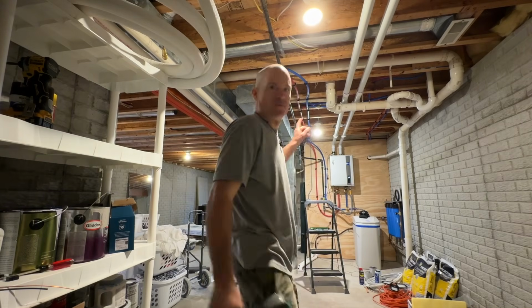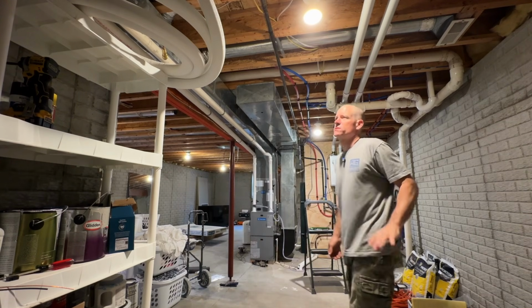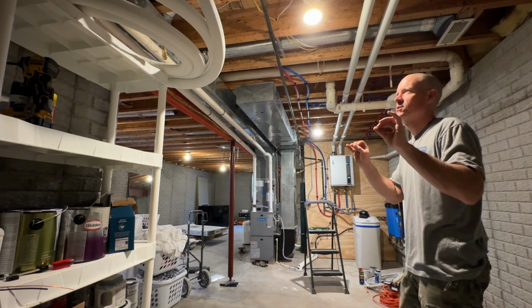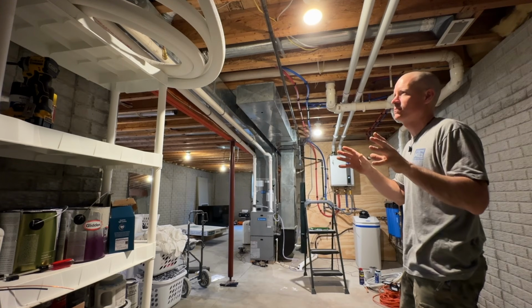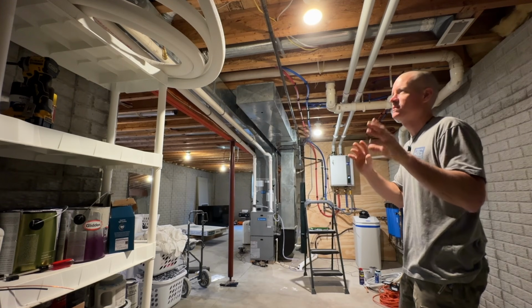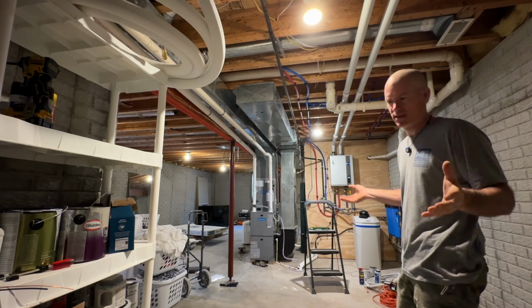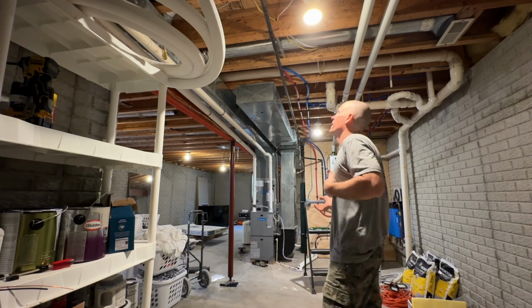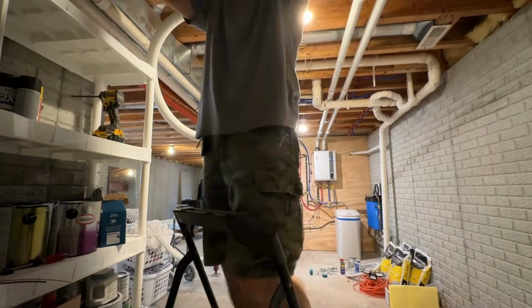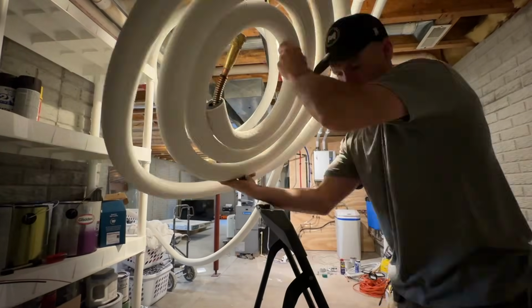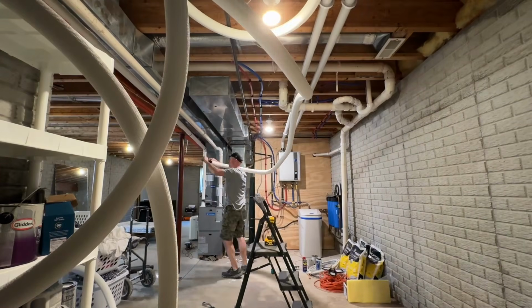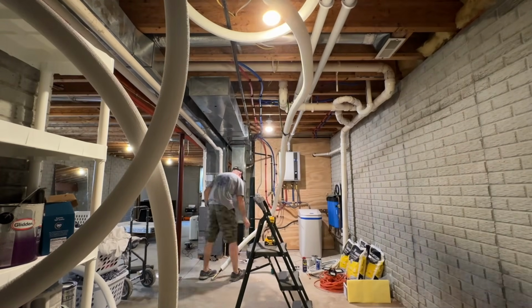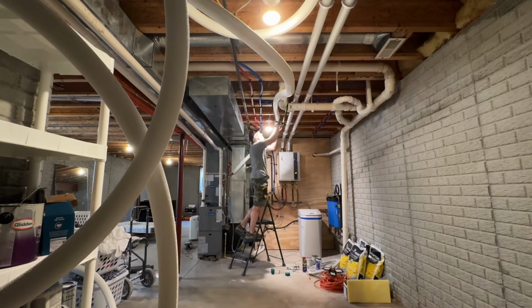All right, I had to take those bright lights out because I couldn't see the ceiling. So this is where the pre-charge line sets, if they're not exactly the right length, you have to do something with the extra, and that obviously can be problematic. I kind of want to coil them up. I'm not going to have a ton, but I kind of want to coil it up here where there's an open space. So I have the line set in.